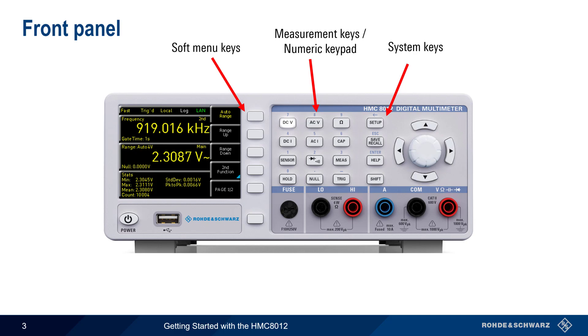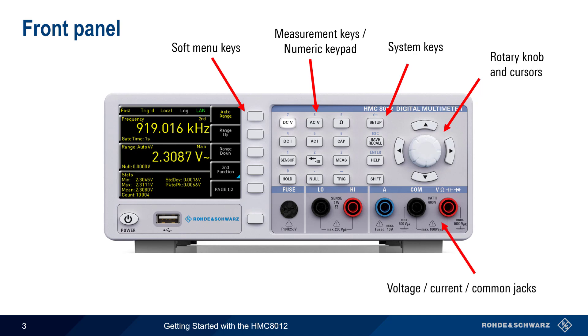The rotary knob and cursors can be used to navigate menus or to change parameter values. Below this are standard size voltage, current, and common jacks, which are connected to the device under test. A pair of sense connectors are also provided for making four-wire resistance measurements, and above these are controls for holding, nulling, and triggering measurements.